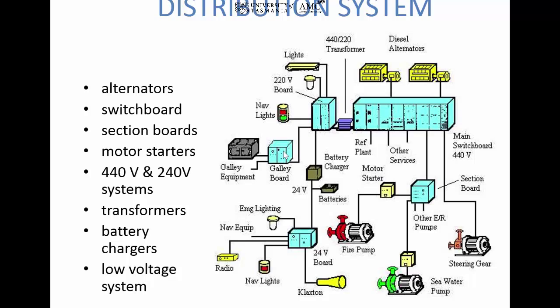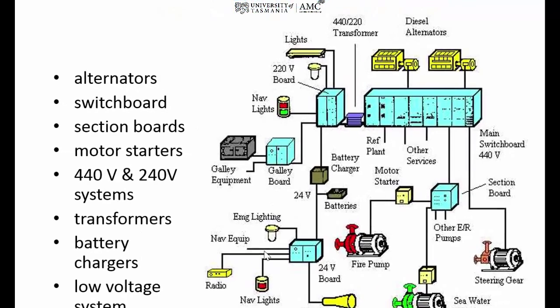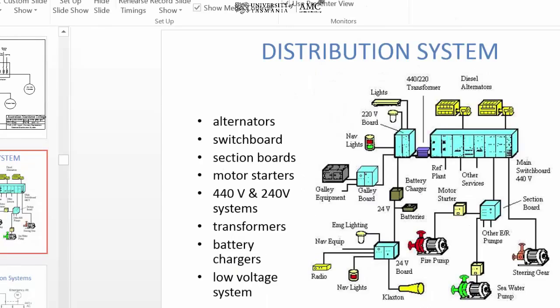And we've got another distribution board here in the galley for our single phase equipment, 240 volts. And then we've got our DC system, so a battery charger here supplying our batteries at 24 volt, and then we've got a 24 volt distribution board which is supplying all of our DC equipment, our emergency gear. So let's have a look at how that might look in a schematic drawing. So bear with me. Alright, so I'm going to sketch that same system up but in a schematic drawing.